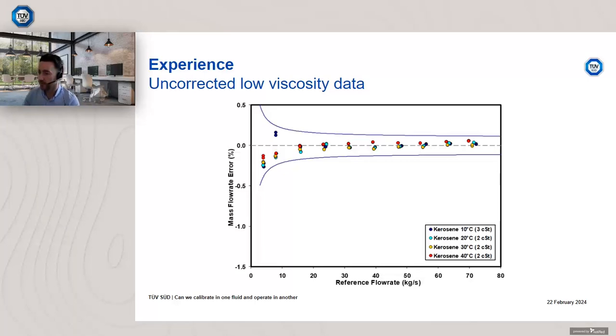On the y-axis we have the mass flow rate error, and that is the deviation between the device under test, in this case a Coriolis meter, with respect to our own reference system with a known uncertainty. I've also overlapped the meter specification, which is the blue line that you can see on the chart. You can see that for uncorrected low viscosity data, this is a brand new meter, pretty much out of the box, just supplied to ourselves and tested. All the data is well within the manufacturer specification.